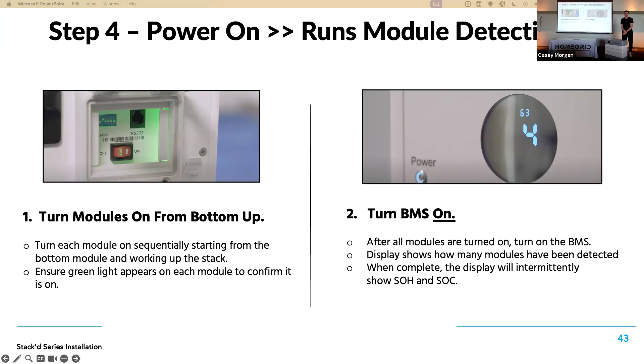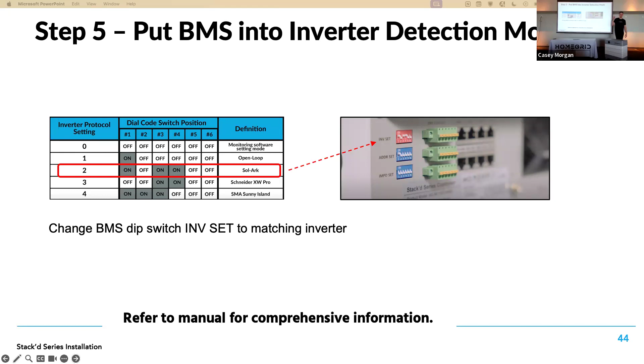We can flip these inverter set dip switches according to the inverter you're working with. Remember, they were all up. Now we just flip them according to the inverter you're working with. So with Sol-Ark, to tell the BMS we're working with a Sol-Ark, you have to set 1, 3, and 4 up, and the rest down.